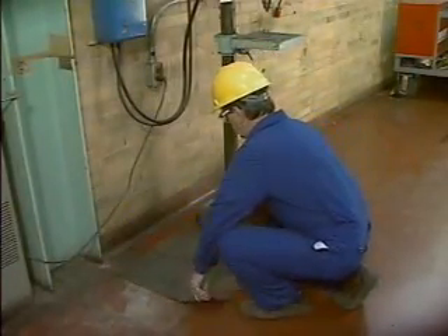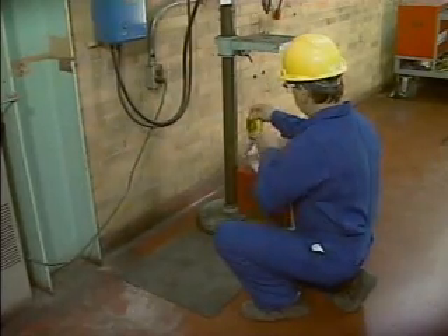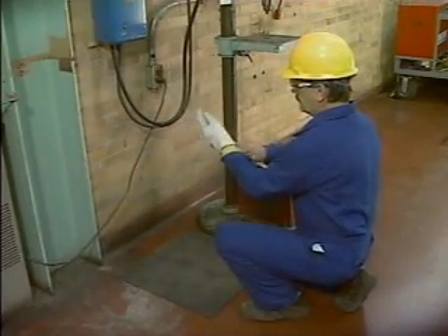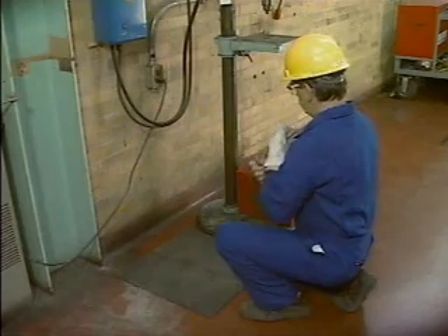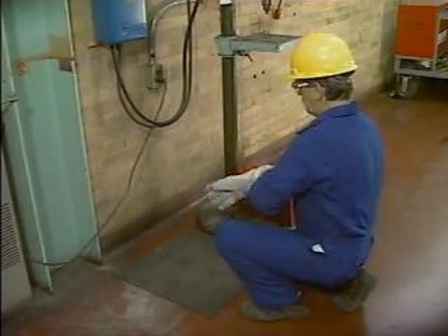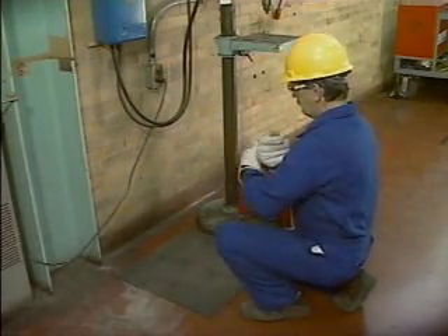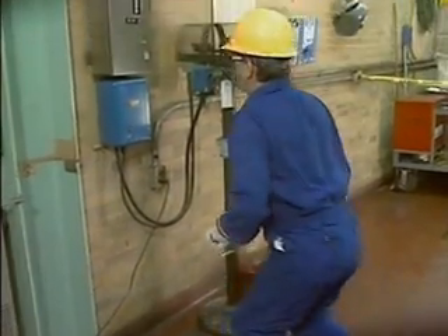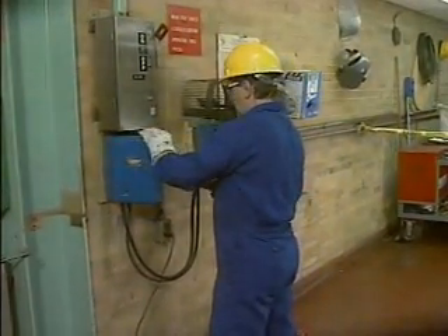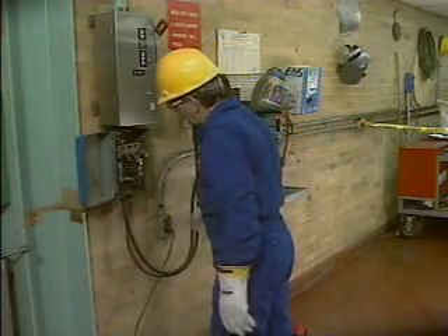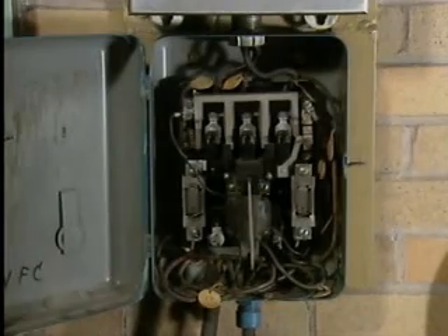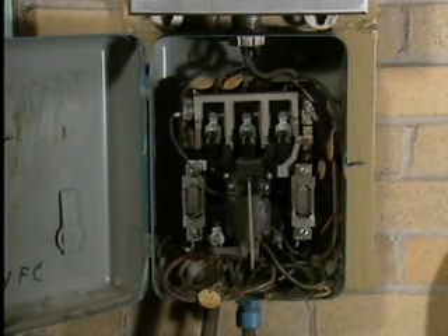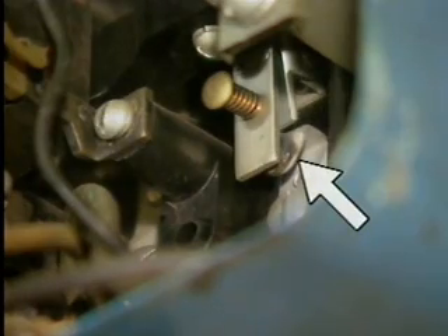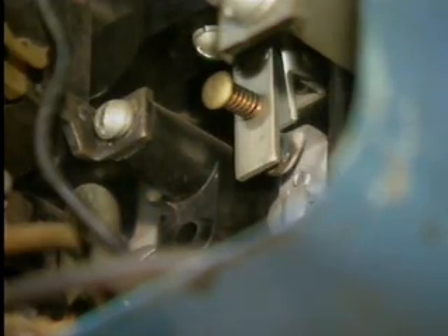Taking this measurement will require the electrician to open the control cabinet door. Because the control cabinet contains energized electrical equipment, the electrician will need to use approved insulating gear to provide protection from electrical shock. After the electrician opens the cabinet door, he takes a moment to visually inspect the components inside. He sees that all of the components, including the thermal overload contacts and the control relay's coil, appear to be in good physical condition. He also sees that the overload contacts are closed.